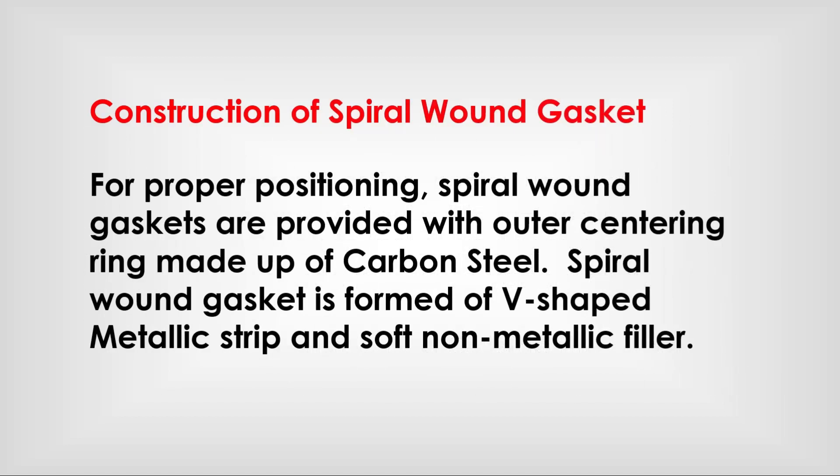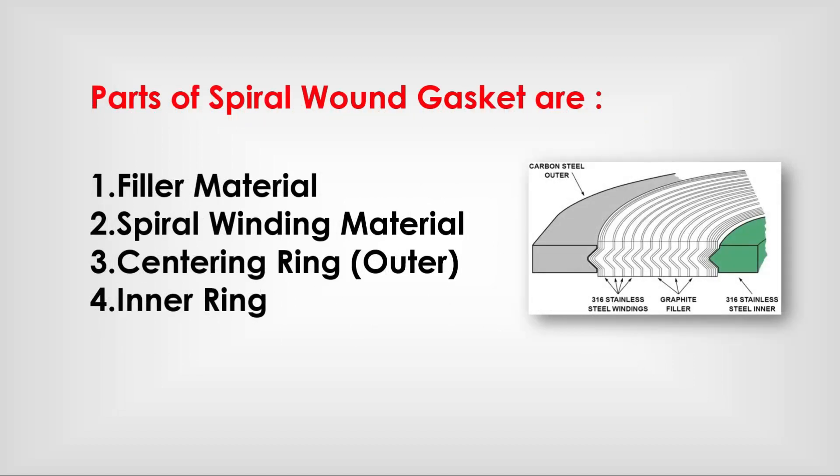Construction of spiral wound gaskets: for proper positioning, spiral wound gaskets are provided with an outer centering ring made of carbon steel. The spiral wound gasket is formed of a V-shaped metallic strip and soft non-metallic filler. Parts of a spiral wound gasket include filler material, spiral winding material, center ring, and inner ring.